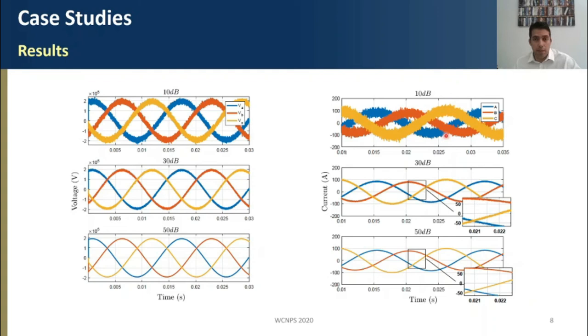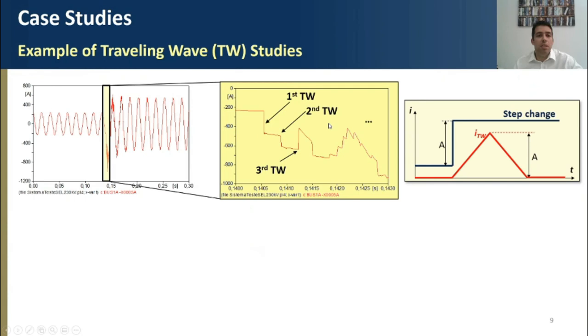And finally, just to demonstrate a practical application, an example of traveling wave studies, if we consider a fault record taken from a current transformer, if we consider a zoomed area here, you'd see in the microsecond timescale some steps. And these steps are related to the moment to which travel waves reached the monitor terminal.